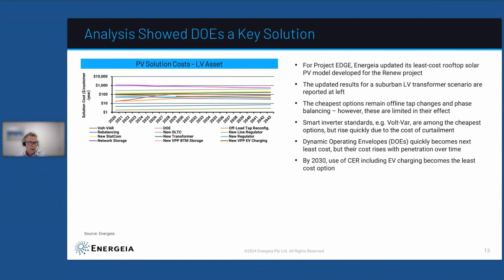we looked at the cost over time of these different solutions. This is just an example of relieving a constraint on a low voltage transformer for an additional incremental investment in solar PV over time. Now, you may not be able to use all of these options over time. Like for example, the lowest cost option here, the offload tap reconfiguration. Once you put them to their maximum values, you have to put in a new transformer basically, or go to online tap changing. Likewise for rebalancing, there's only so much rebalancing you can do. Both of these are relatively low cost.